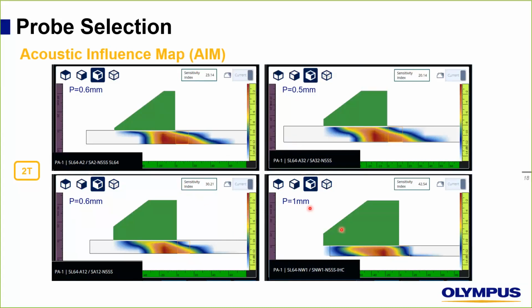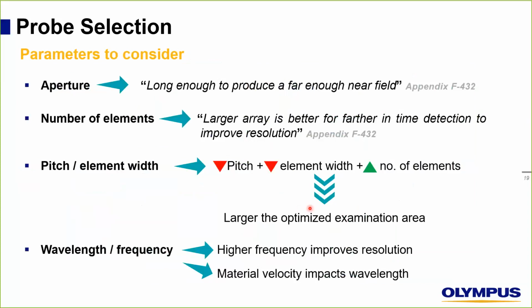So here we understand clearly that the parameters of the probe are very important in the selection of the right one. So let's have a look at how the code talks about these parameters of the probe. What are the parameters to consider? First, we have the aperture. The larger it is, the longer the near field will be. Actually, I kept the definition as it is in the code, but I will explain it in my own words. For number of elements, generally, higher numbers provide better resolution. For pitch and element width, because they are very related, small pitch, small element width, and a large number of elements provide a large optimized examination area.